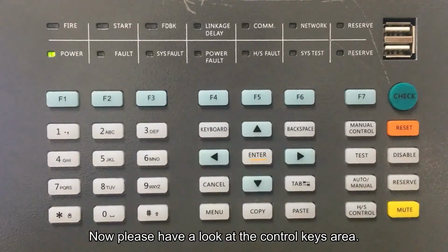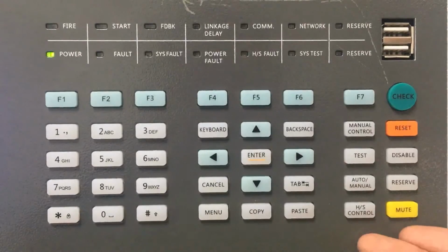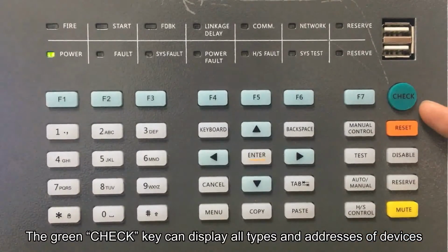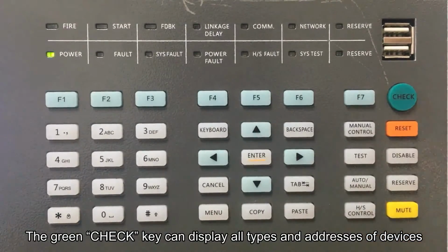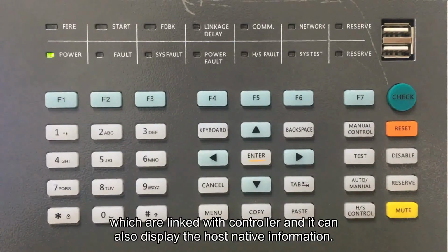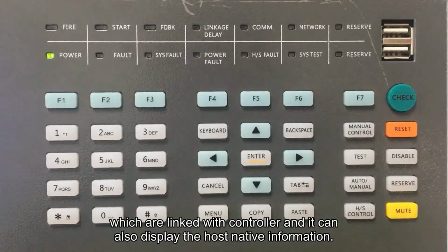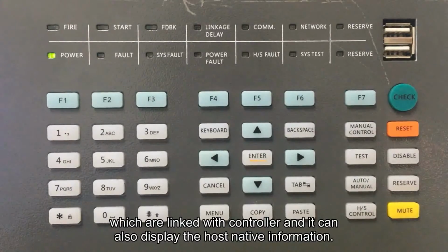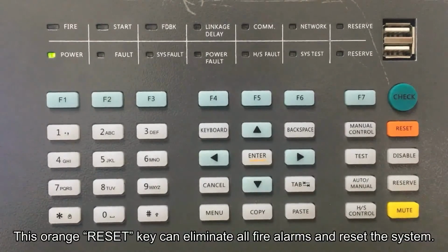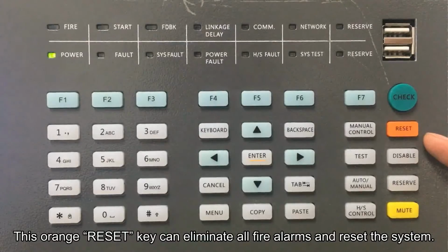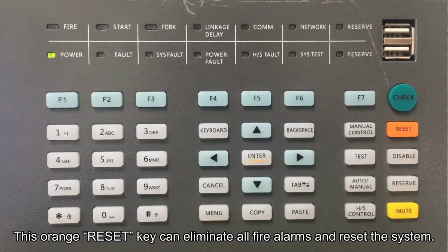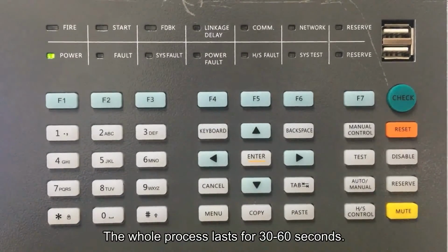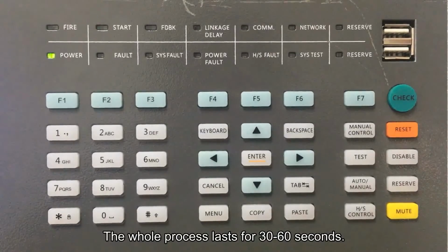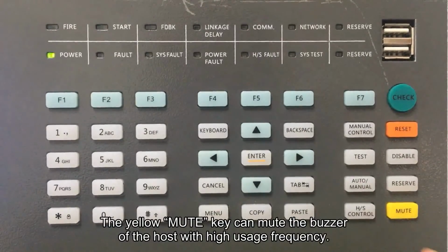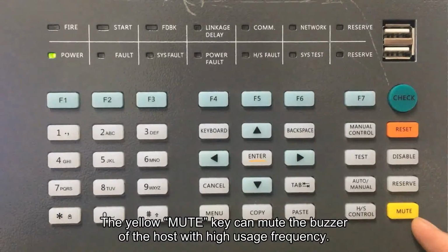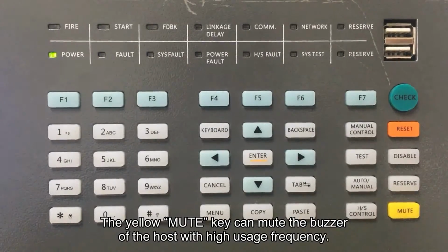Now please have a look at the control keys area. The green check key can display all types and addresses of devices which are linked with controller, and it can also display the host native information. This orange reset key can eliminate all fire alarms and reset the system. The whole process lasts for 30 to 60 seconds. The yellow mute key can mute the buzzer of the host with high usage frequency.